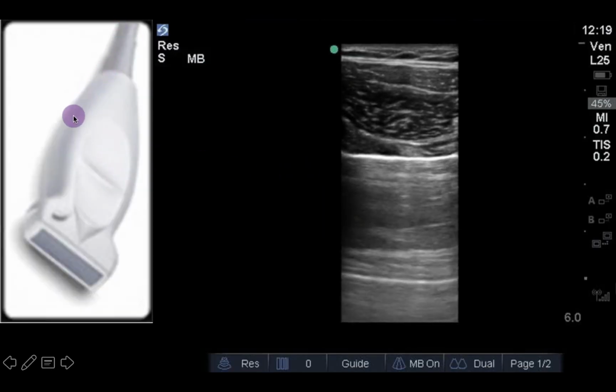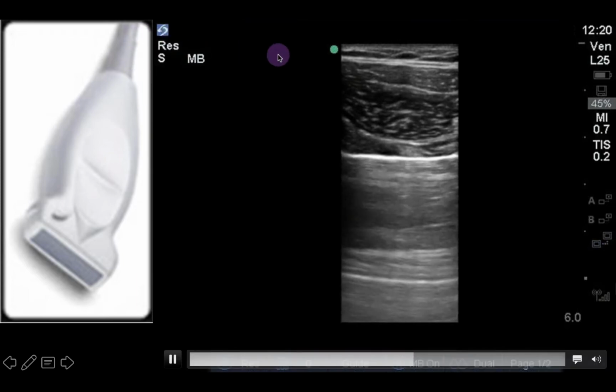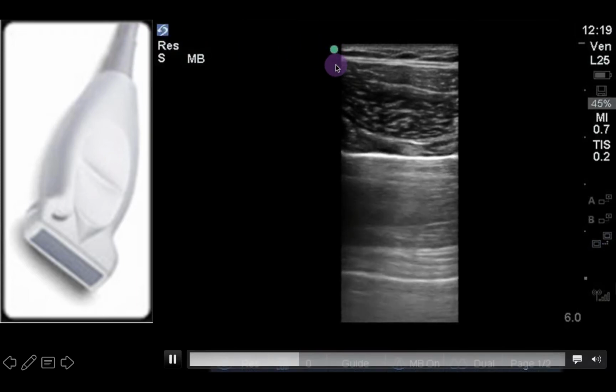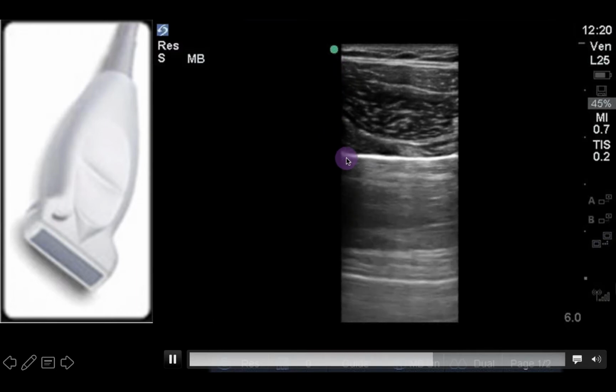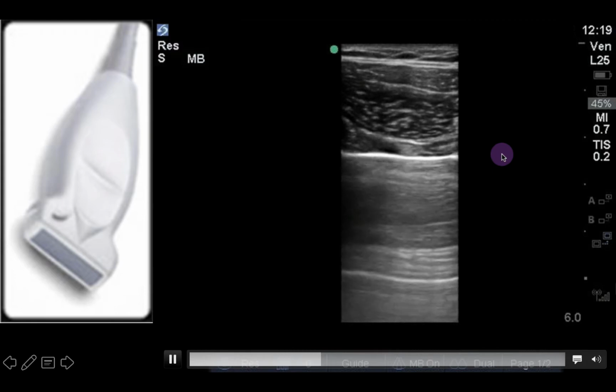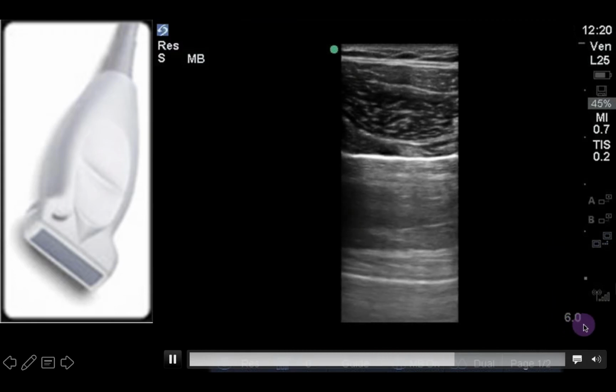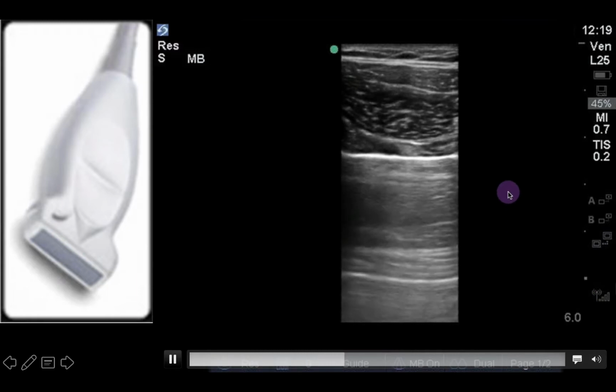You'll recognize the linear probe if you've ever used it to assist you in arterial or central venous line insertion. It is a high-frequency probe, usually in the 6 to 13 megahertz range, which allows for high-resolution images of superficial structures down to about 5 centimeters. This is often useful for accessing superficial blood vessels or for imaging the pleura.